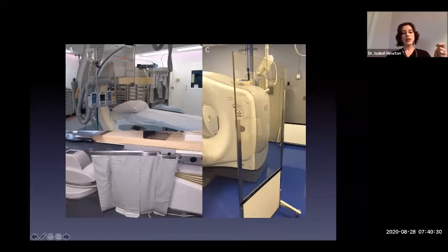And then you can also decrease the scatter radiation to yourself by using disposable shields that are basically a drape that's impregnated with some material that blocks the scatter radiation. The important thing though with these is you don't want to include them in the field of view because they will increase your dose, because remember that automatic exposure control will pump out more photons to drive through these things that are blocking it. Here's that skirt, the gonad saving skirt. You should make sure that that's always hung up and is in place.